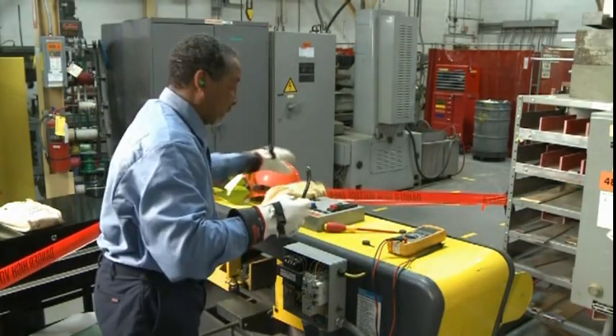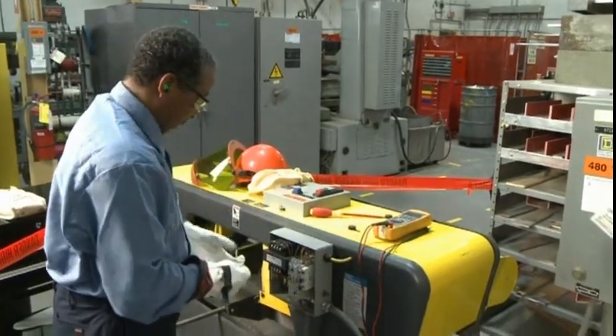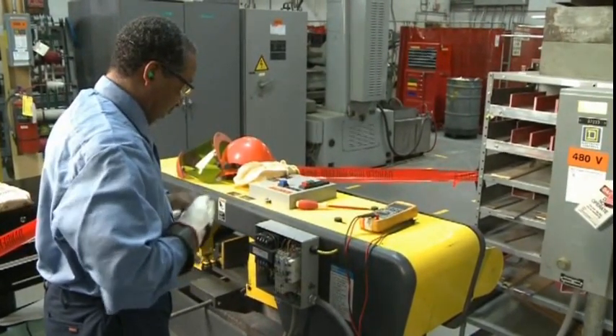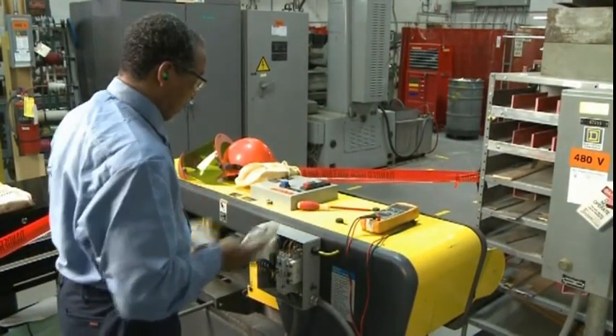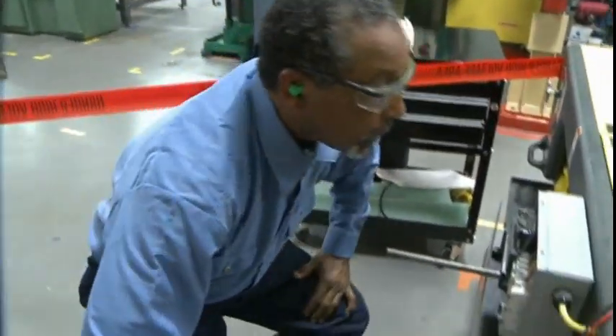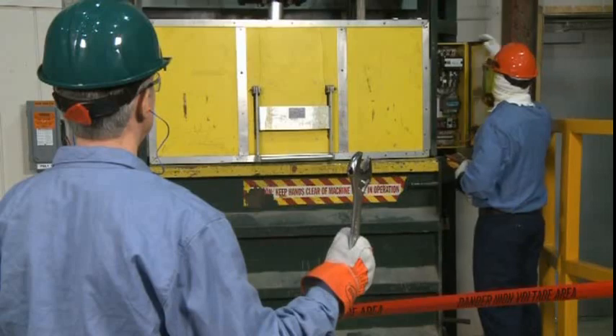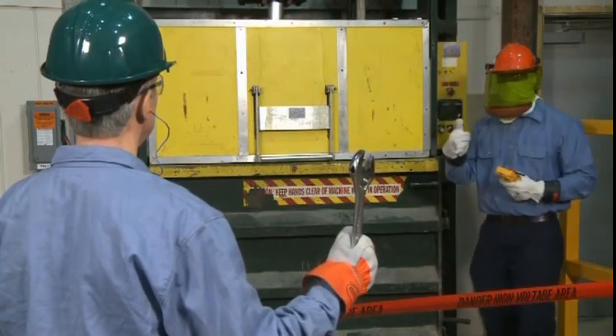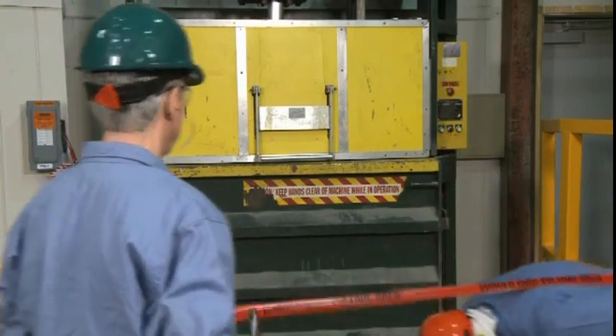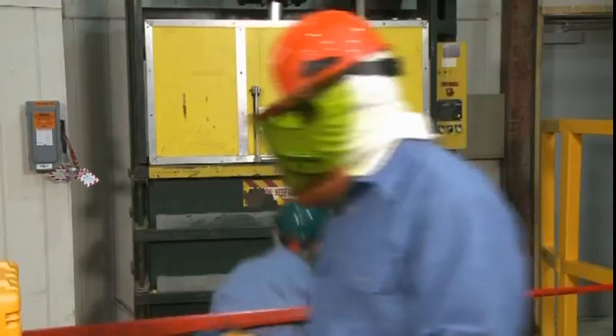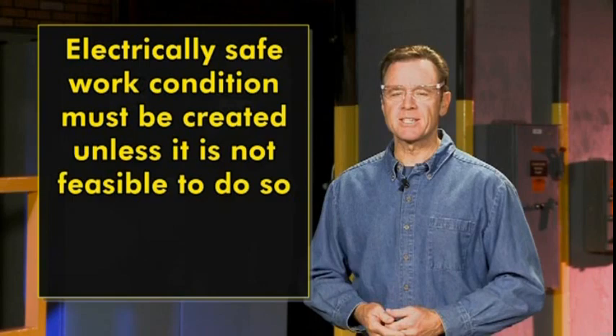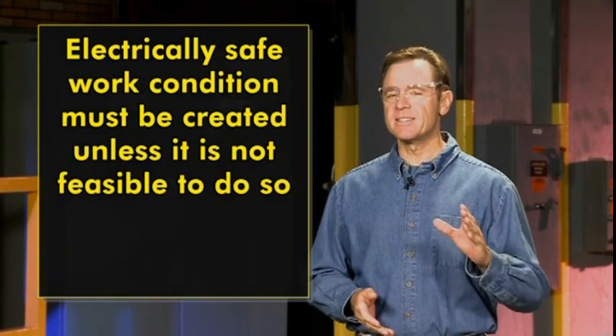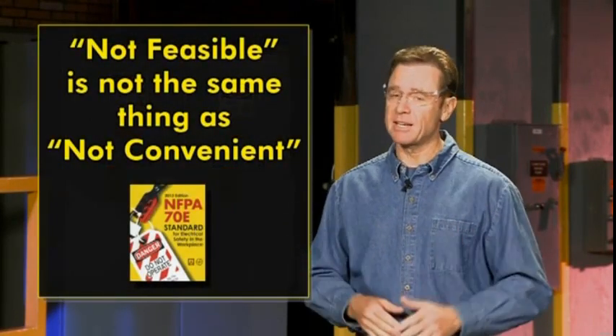However, once an electrically safe work condition is created, no electrical hazards exist. This means that shock and arc flash protection are no longer necessary and may be removed. This also means that other workers who are not qualified electrical workers may enter the area as needed. Again, creating an electrically safe working condition is always the preferred method to ensure your safety. In fact, the NFPA 70E requires that an electrically safe work condition be created unless it is not feasible to do so. And just remember that not feasible is not the same thing as not convenient.